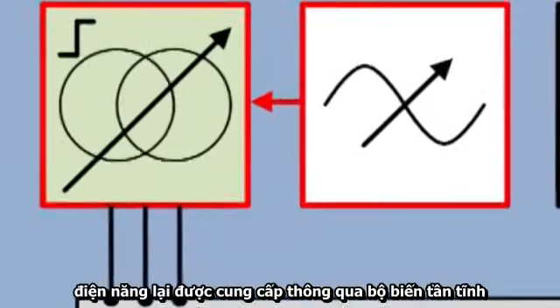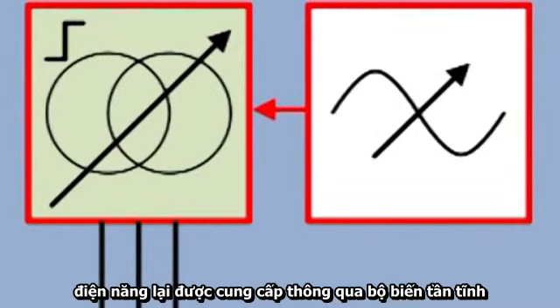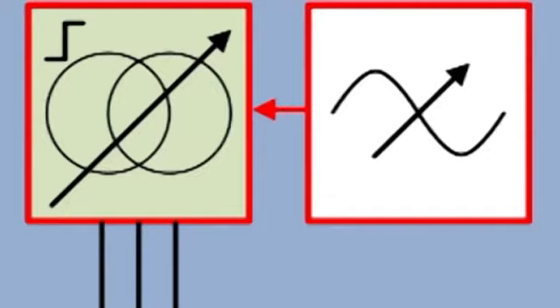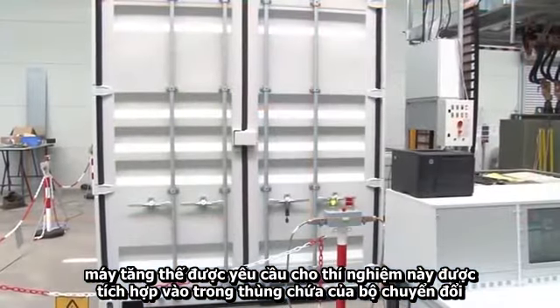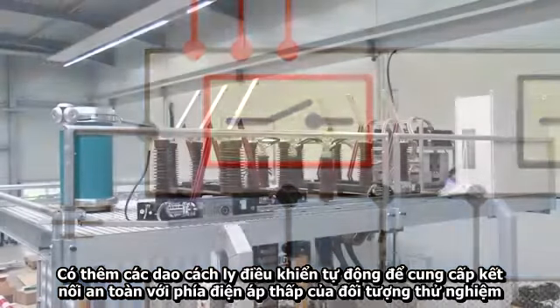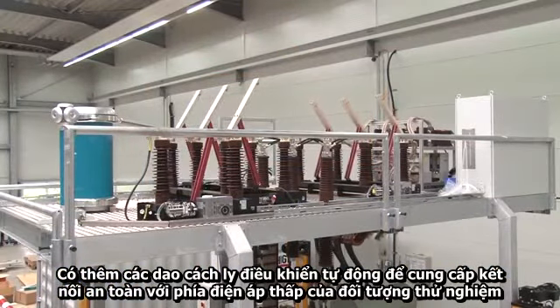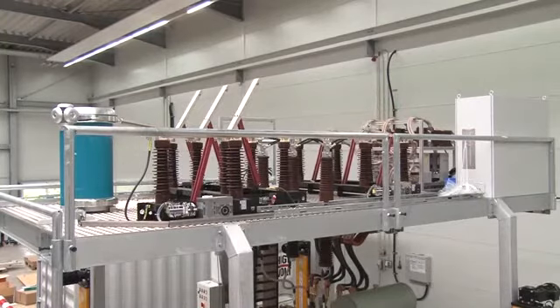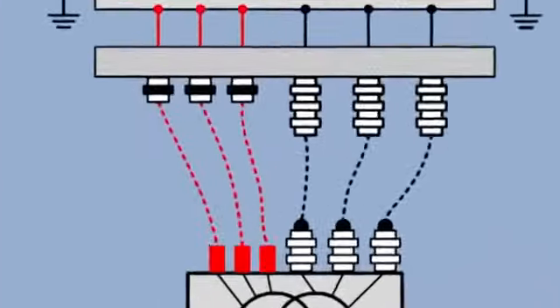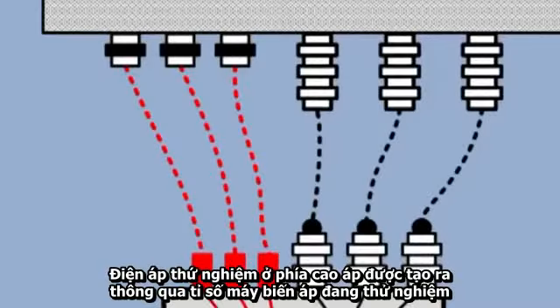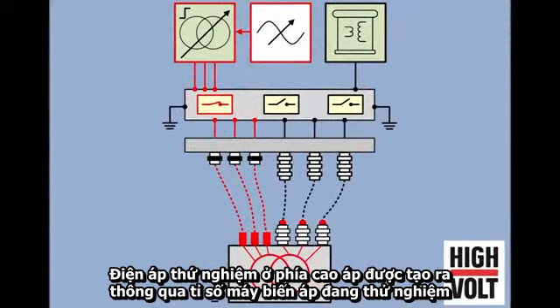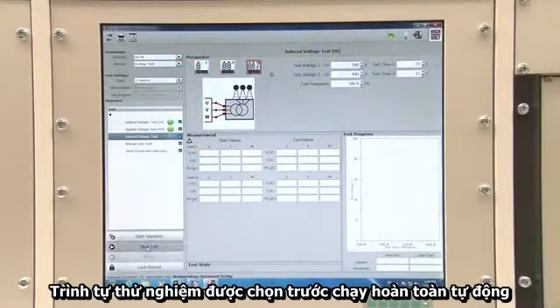Induced voltage test. The power is again supplied via the static frequency converter, but in this case, with a higher frequency. The step-up transformer required for this test is integrated into the container of the converter. There are further automatically controlled disconnectors to provide a safe connection with the low voltage side of the test object. The test voltage on the high voltage side is generated according to the ratio of the transformer under test. The pre-selected test sequence runs fully automatically.